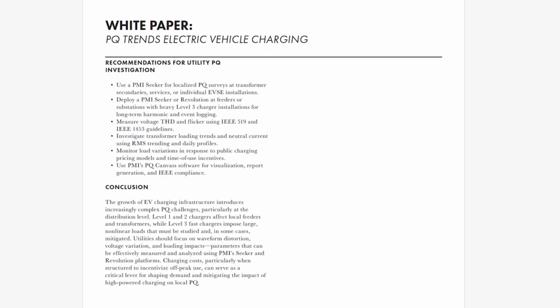If the voltage is in excess of the 519 standard, then the utility would need to mitigate that, often by detuning capacitors or finding other customers on the system that are in violation of 519, or decreasing that system impedance, upsizing the transformer, upsizing conductors. But that really depends a lot on the relationship between the voltage and the current and which side is causing more distortion.